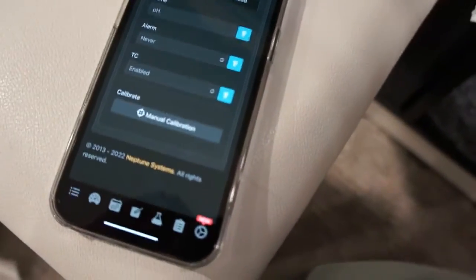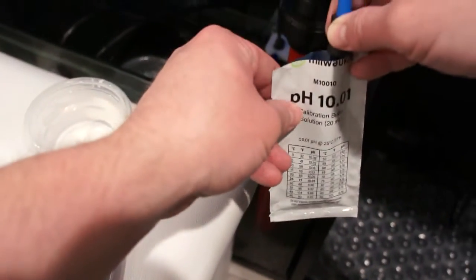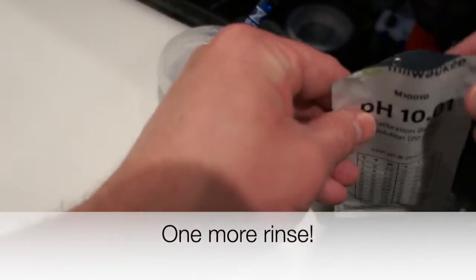You're going to return to where you were and go back to the dashboard view — there we see the pH has jumped up to 10. Slowly remove the probe from the solution, go back to the RODI water cup for a little rinse, and then take it straight back to the sump and get it in the probe holder. Be careful — sometimes people over-tighten their probes with those little plastic nuts and it can crack or damage the probe, so a word of caution there.